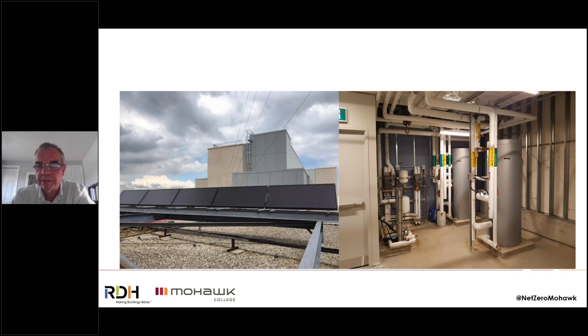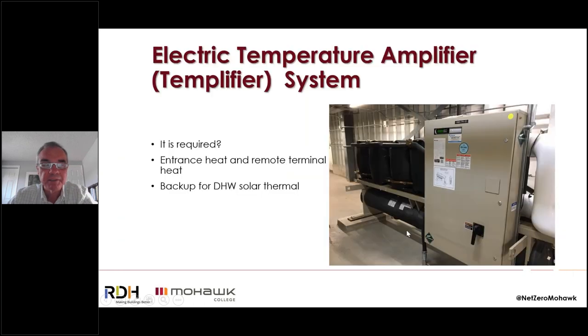Through some studies, in a student project, we found that the piping coming in through the wall or floor here had gotten crossed - supply and return got mixed up, which is why we weren't getting the performance we wanted when testing. The students actually found this out and said these things could be switched. So I met with Viessmann, the supplier - it wasn't their issue, it was a mistake. We worked on it and found the solution: a simple fix of crossing the piping again, and got it properly installed. But those are the things that happen.